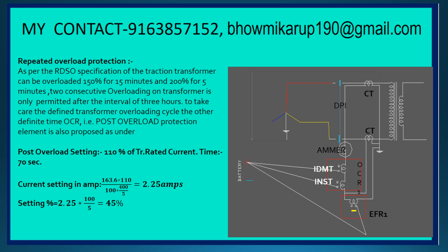As per the traction transformer RDSO's guideline, our power transformer can withstand 150% overload for 15 minutes and 200% overload for 5 minutes. And also 2 consecutive overloads on the transformer are only permitted after an interval of 3 hours.